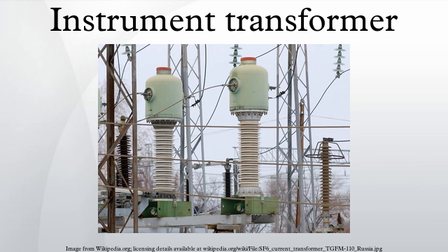A current clamp uses a current transformer with a split core that can be easily wrapped around a conductor in a circuit. This is a common method used in portable current measuring instruments, but permanent installations use more economical types of current transformer. Specially constructed wideband CTs are also used, usually with an oscilloscope, to measure high-frequency waveforms or pulsed currents within pulsed power systems.